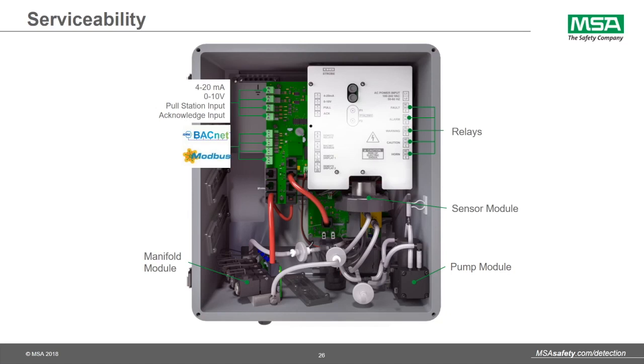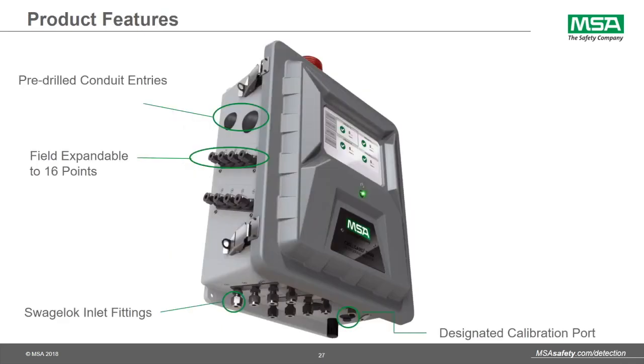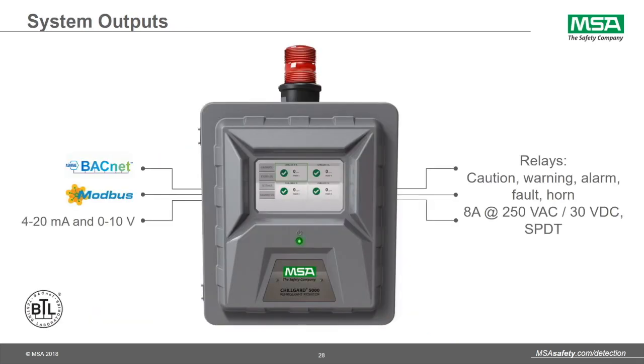Serviceability is another important feature. Our monitor is based off of a modular design that can be easily repaired and upgraded out in the field. Each module works off of its own board that is field serviceable. Some of the physical product features include pre-drilled conduit entries, field expandable valve modules, robust Swagelok inlet fittings, and a designated calibration port that makes calibration really easy.